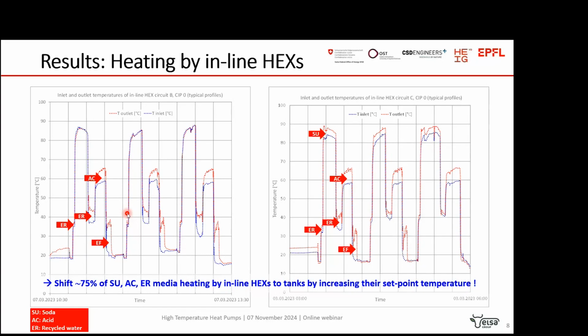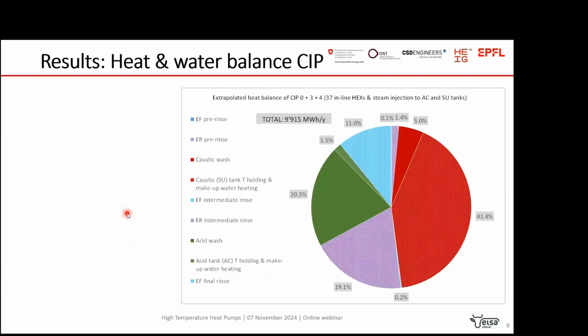That was the idea. Regarding the heat and water balance, we also measured what happened around the caustic and acid tanks, to see how much heat was supplied to hold the temperature and how much makeup water was supplied. We got this diagram: here in red is the temperature holding of the caustic tank, which is responsible for over 40% of the steam consumed.